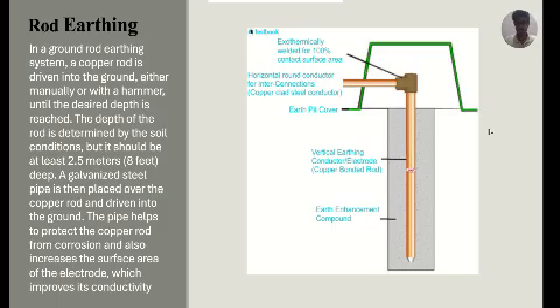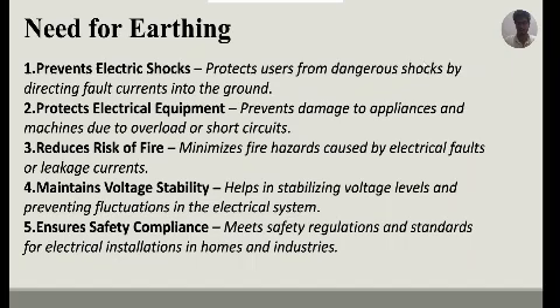So why do we need earthing? What is the necessity of earthing? Let's discuss. It prevents electrical shocks. It protects electrical equipment, and it prevents damage to machines due to overload or short circuit conditions. It also reduces the risk of fire and fire hazards caused by electric or leakage currents. It maintains the voltage in a stable condition and prevents fluctuations in the electrical systems. It also ensures safety and meets all the safety regulations for electrical installations in our homes.